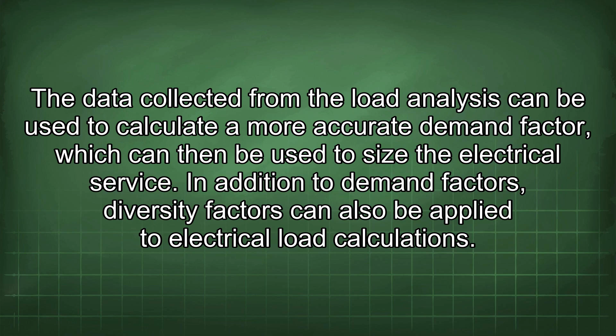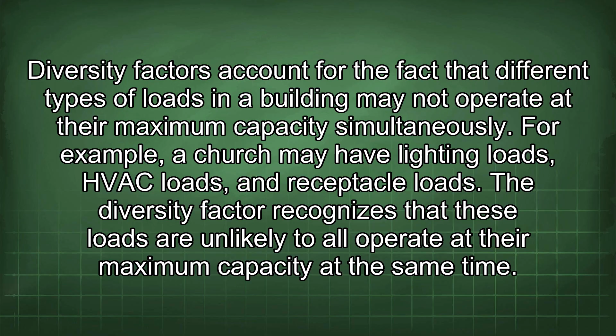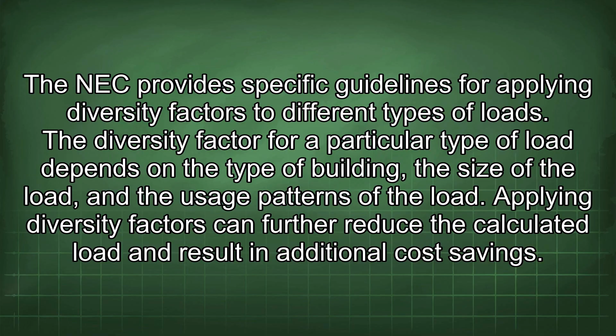capacity simultaneously. For example, a church may have lighting loads, HVAC loads, and receptacle loads. The diversity factor recognizes that these loads are unlikely to all operate at their maximum capacity at the same time. The NEC provides specific guidelines for applying diversity factors to different types of loads. The diversity factor for a particular type of load depends on the type of building, the size of the load, and the usage patterns of the load. Applying diversity factors can further reduce the calculated load and result in additional cost savings.